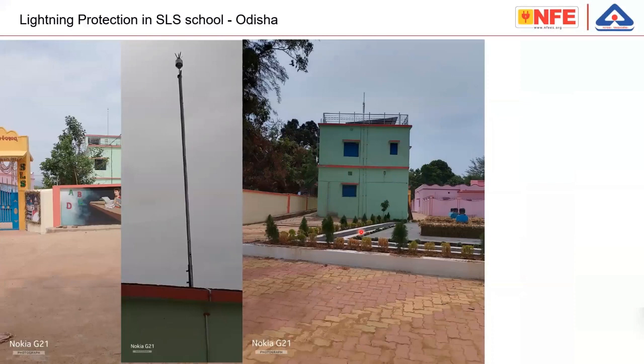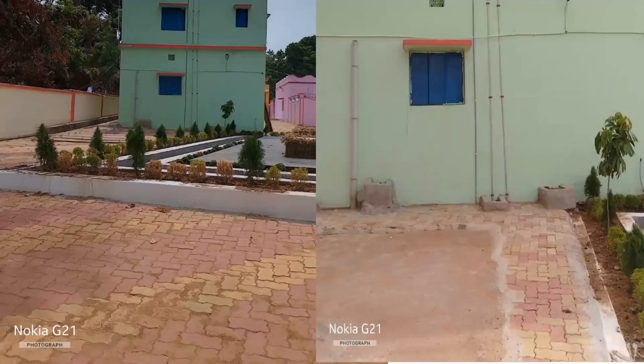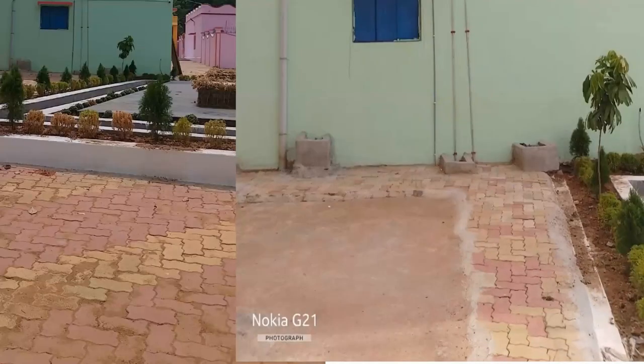So even the standard says you have to keep only 3 meters away from a down conductor. Please note that that is applicable to a building where lightning protection as per 62305 is installed. Whereas in this particular building, lightning protection is installed as per a story, not as per a standard. One down conductor here, probably you should keep 10 meters away, like the tree. You must keep 10 meters away from this particular conductor, otherwise it is going to create a real hazard. Then the down conductors are connected to an earth electrode. As you can see here, there is a pipe or a plate or something like that, most probably a pipe. Each down conductor is connected to a rod, one down conductor connected to one rod.